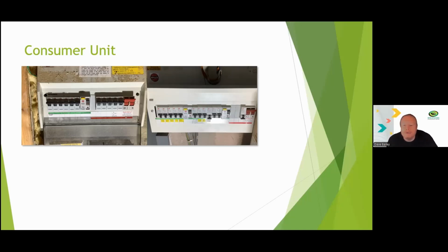You can also have an RCBO, and that combines the circuit breaker from the normal switches with an RCD in just one unit. The advantage is that if it trips, it only trips that one circuit and doesn't knock half the house out like an RCD would. It's a bit more expensive for an RCBO though, so not the most cost-effective way of doing it.